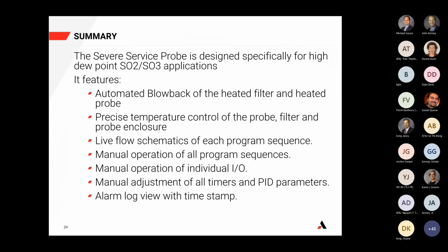I guess in summary, this is a high dew point specific application. This is not something you use for your normal everyday, very low dew point applications. We offered the automated blowback of the heated filter and heated probe, the precise temperature control of the probe filter and probe enclosure. It has a live flow schematic of each program sequence and permits manual operation of all the program sequences, as well as manual operation of the individual IOs as well, including all timers and PID parameters.